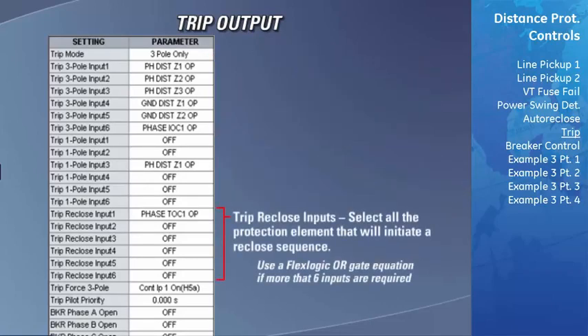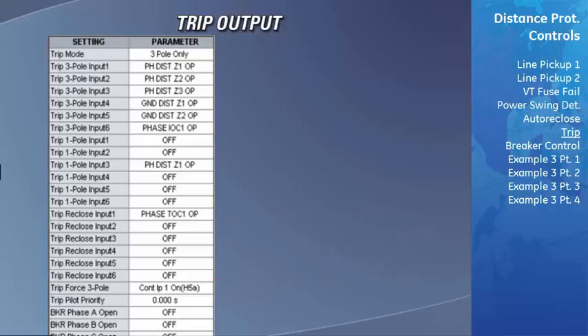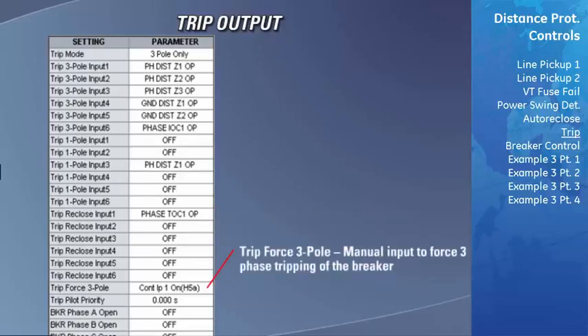The next 6 fields are labeled Trip Reclose Inputs 1 to 6. In these fields, you need to enter all of the types of faults that you wish to initiate a reclose after the breaker has been tripped by that protection element. If you require the ability of selecting more than 6 inputs to initiate a reclose, you will need to create a flex logic equation where all of those additional inputs will be ORed together, and then assign that virtual output to this list.